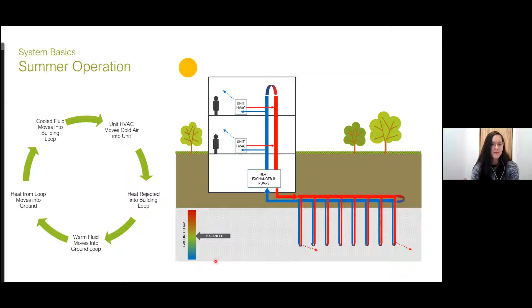Near the surface, the Earth's temperature fluctuates with the season, but in its natural state, a few hundred feet down, the ground temperature is essentially constant. If the balance of the Earth's temperature deep within the ground where the geothermal wells are located is maintained, the system will just work in perpetuity. It'll just keep going. But it's when things aren't balanced and when that overall temperature of the ground surrounding the well system isn't maintained that you start to potentially see problems with your system.